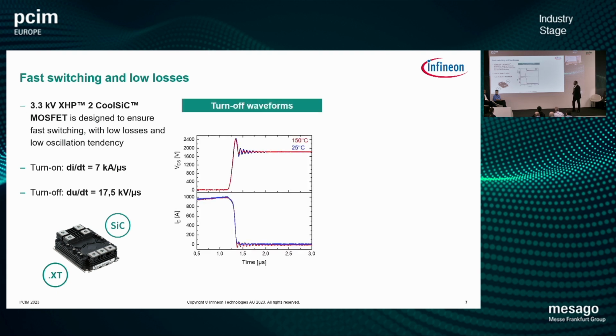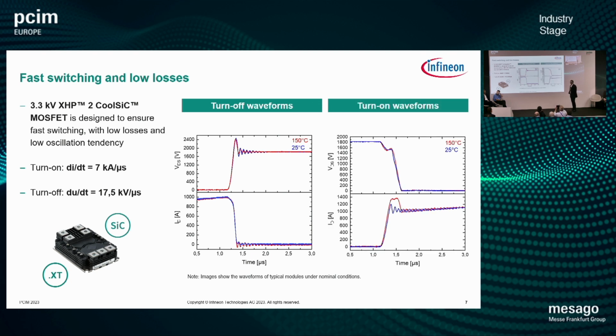And what you clearly see is that because we have a low inductive housing, the turn-off switching transients are almost negligible, or very low, compared to if the design is put into a high inductive module. And the same is true for the turn-on behavior. We see from the temperature absolutely no dependency of the turn-off losses. This is in the range of around 180 millijoules for 1000 amperes, and around 450 millijoules for the turn-on energy.